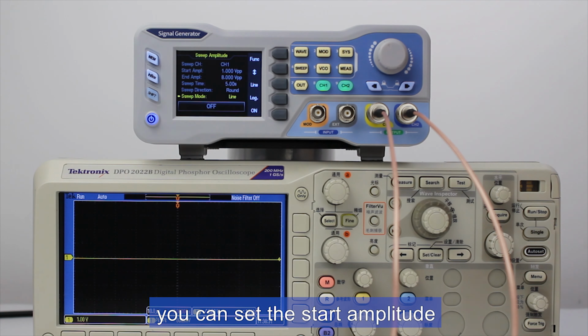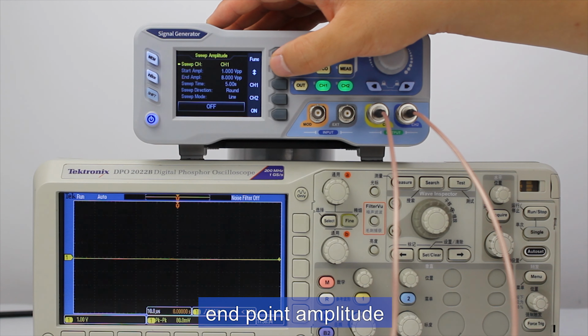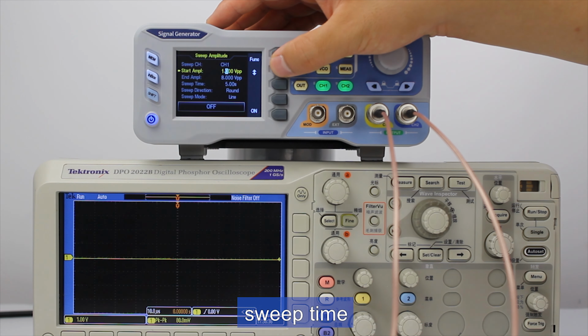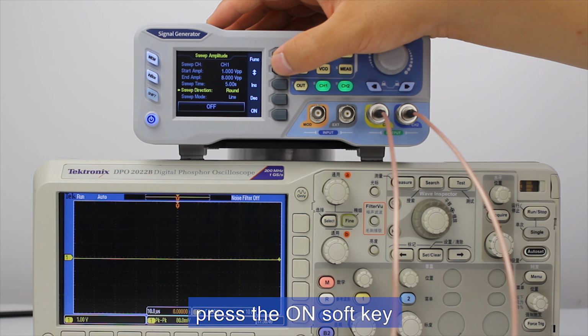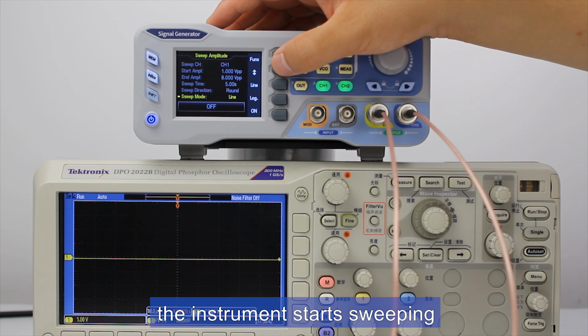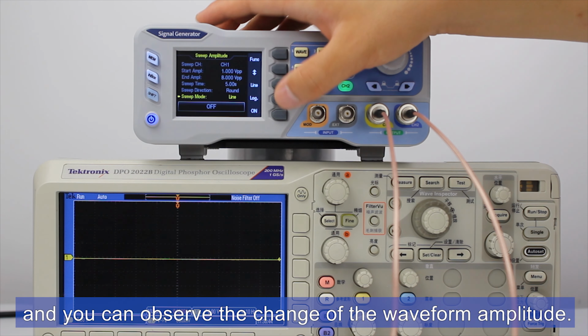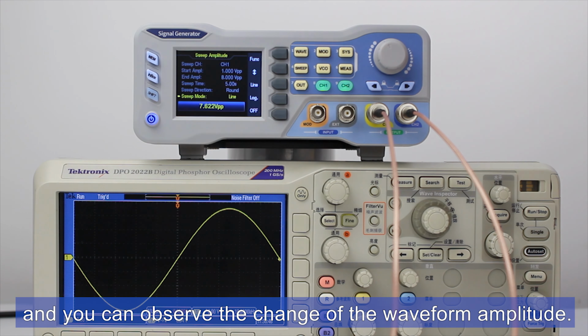Switch to the amplitude sweep function. You can set the start amplitude, endpoint amplitude, sweep time, sweep direction, sweep mode. Press the on soft key. The instrument starts sweeping, and you can observe the change of the waveform amplitude.